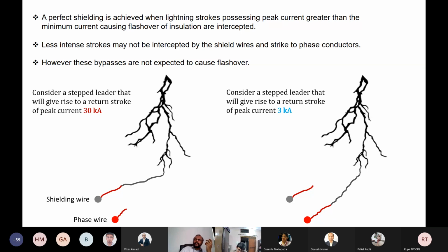So this is another important thing. If you have shielding wires, the chances of a low amplitude current getting attached to the live wire bypassing the shielding wire is higher. Or in other words, shielding failure happens for low amplitude currents more than for high amplitude currents. What does that mean? It means that even though there is a shielding failure, if there is a shielding wire, the backflashover is quite low in probability in a distribution system. So that emphasizes the importance of shielding wires.